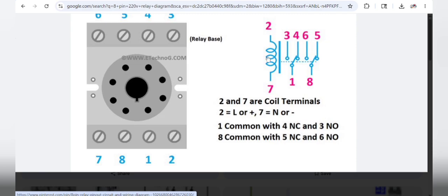When the relay is energized from your input 220 or 110 volt, this normally closed contact will break, and pin number 1 will close with pin number 3, and pin number 8 will close with pin number 6. So you take a 12 volt or 24 volt DC power supply and give the negative feed to this wire, and check from pin number 4, or you can use this other contact. Pin number 8 is your common and pin number 5 is your normally closed contact.